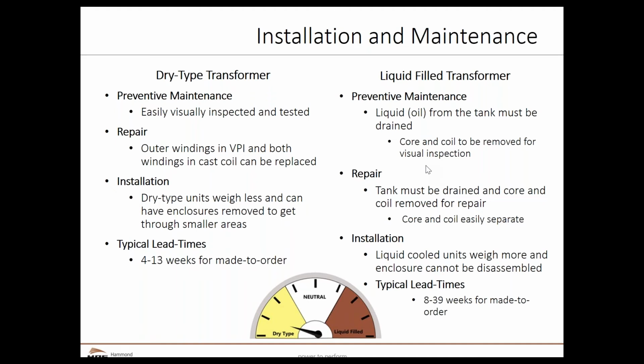Installation-wise, dry type units typically weigh less, and their enclosures can be removed. This is a really important consideration, especially interior. I can take a dry type transformer, completely disassemble the enclosure, bring the core and coil through a door and then reassemble the enclosure inside. With a liquid filled, I don't have that option. It's a welded steel enclosure, and it may be some difficulty getting around corners or through doors.